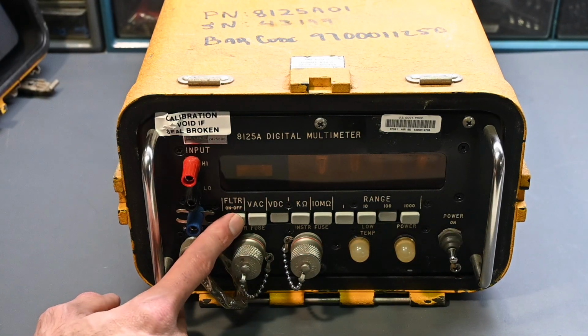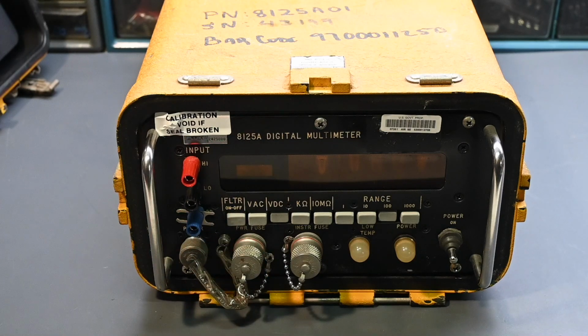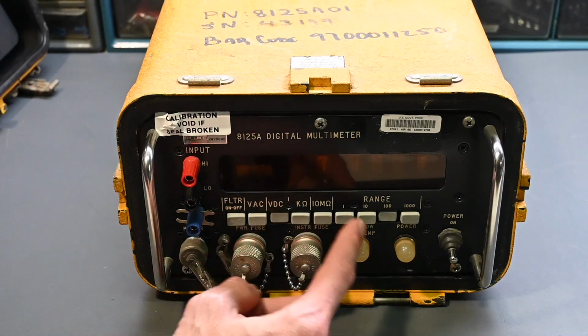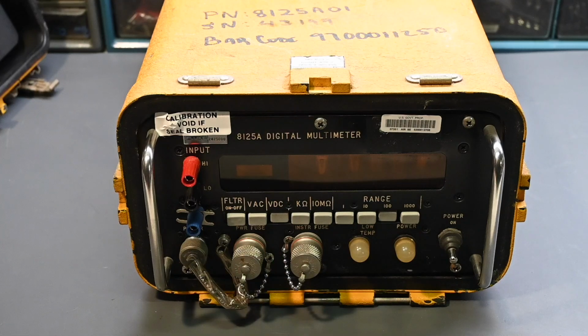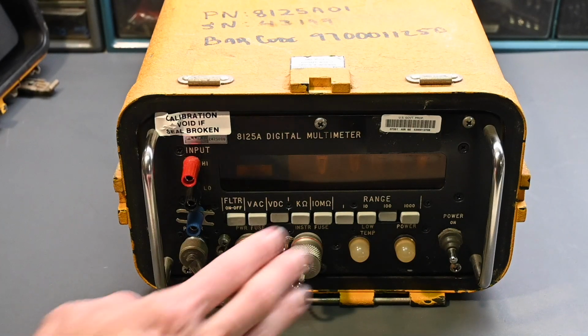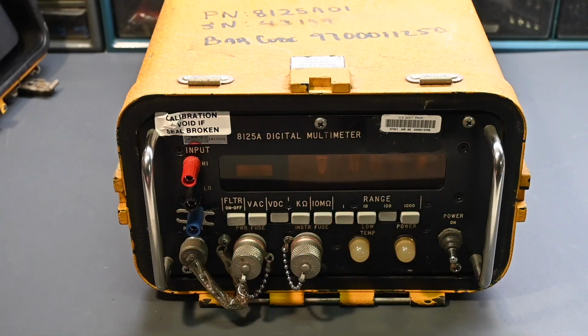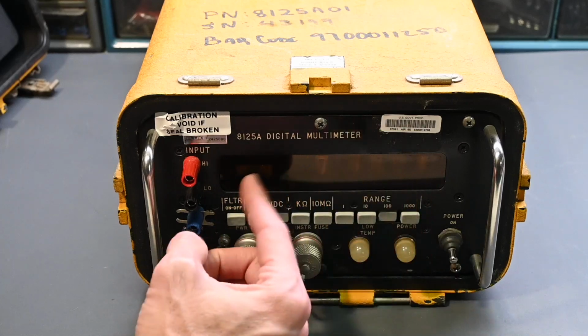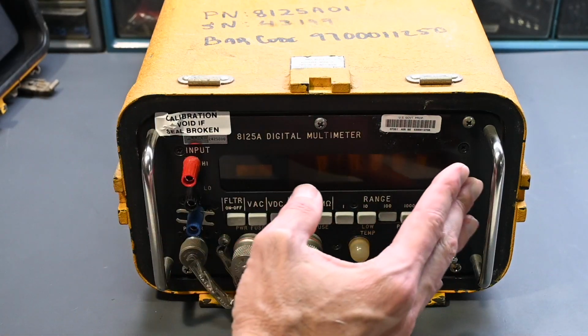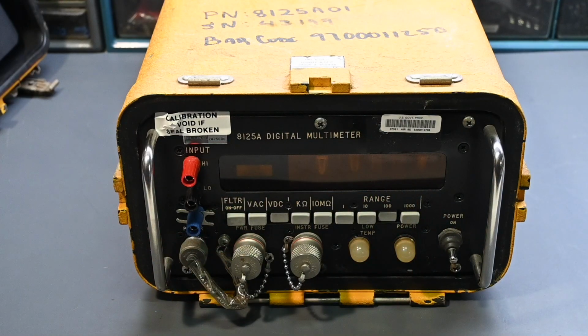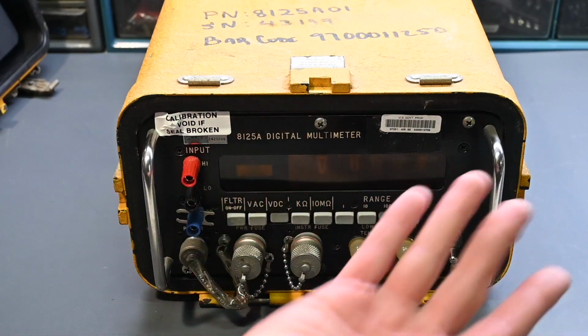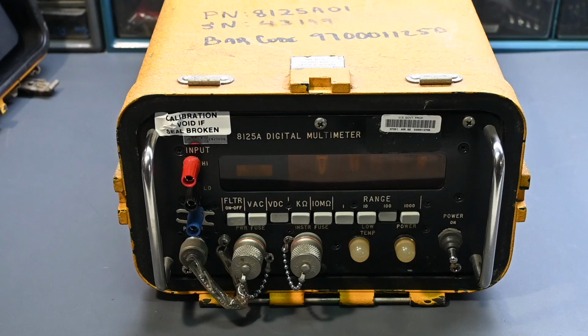There's a filter right here, an active type noise filter. So you have AC volts, DC volts, ohms, with the range selector over here. The display window is hard to see on camera, but it has a very fine wire mesh embedded in the glass that keeps interference from going into or coming out of the meter. Without that mesh, this would basically be a hole in the instrument, so they wanted to shield it both internally and externally.